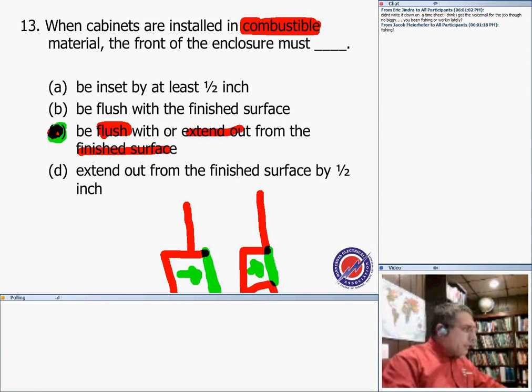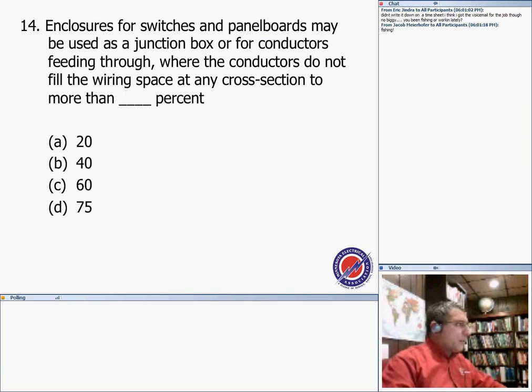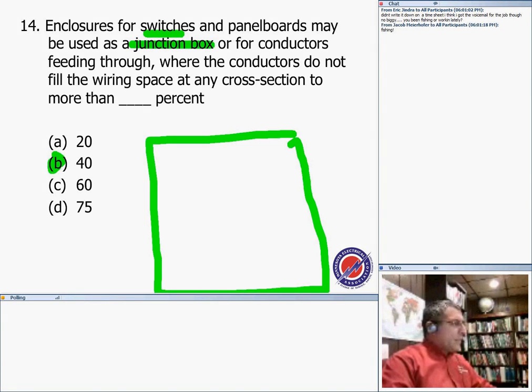A lot of you got number 15 wrong, so mark it. Number 14, enclosures for switches. Panelboards may be used as a junction box. Can I use it as a J box? No problem. Bring it on. Or for conductors feeding through, where the conductors do not fill the space at a cross-sectional area of more than just the conductors passing through. Number 14 is 40%. So I use 40% of the gutter, then with my panel, and I pull my conductors.